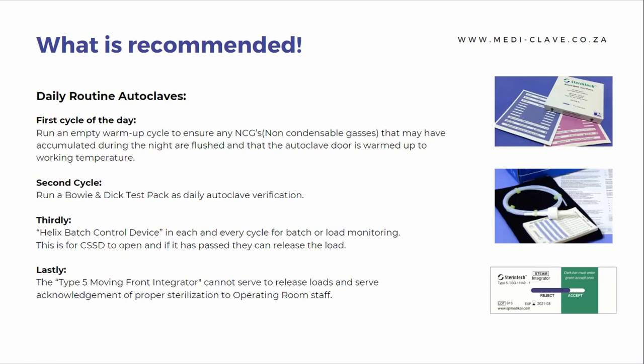Then thirdly, your Helix batch control device needs to be placed in every single cycle as your batch control or load monitor. So that is specifically for your CSSD staff. And if it has passed, they can confidently release the rest of their load, bearing in mind though that the type 5 moving front integrator still needs to be placed in each and every single pack. That's not for CSSD, it's still for the operating room staff to acknowledge proper sterilization.